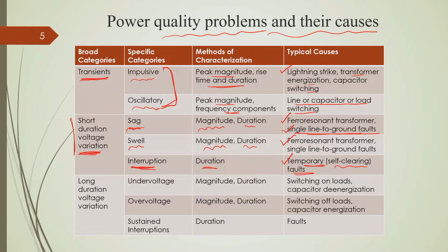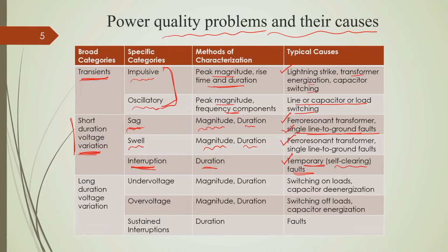As I said, distribution networks encounter many faults due to non-technical reasons. One of the reasons is weather related or animal related issues. If at any instant a branch of a tree located near the distribution line suddenly touches one of the phases of the distribution line, it may cause a transient type of fault. Within a few seconds or even a microsecond they get detached, and thereby create a transient fault which is self clearing. This may sometimes cause voltage sag and voltage swell in other phases and also cause voltage interruption.